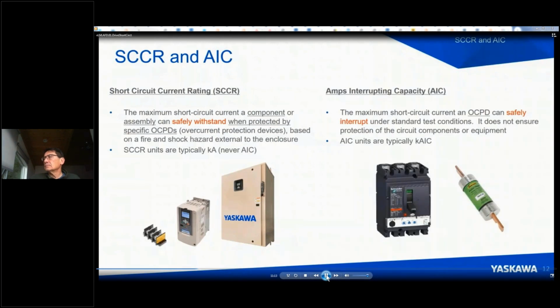Then we have amps interrupting capacity. Amps interrupting capacity is the maximum short circuit current that an overcurrent protective device itself can safely interrupt. You see on the left-hand side, SCCR is safely withstand. On the right-hand side is safely interrupt. The amps interrupting capacity units are typically AIC or kAIC. So again, on the left-hand side, assemblies or components such as drives or terminal blocks, things that aren't meant to interrupt the current, are expressed in kA. On the right-hand side, these devices are expressed in AIC because they are interrupting devices. So hopefully that clears that up.